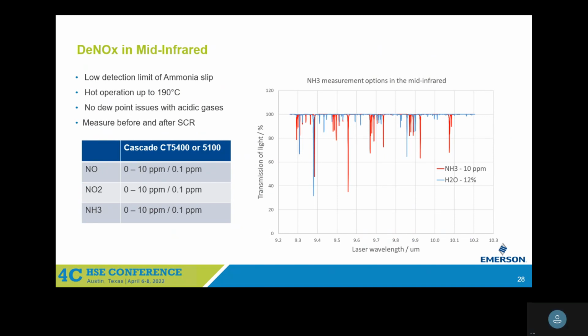A little bit about ammonia. Ammonia slip has traditionally been measured nowadays with tunable diode lasers cross stack. The reason is to avoid an extractive system with a molecule as sticky as ammonia. So they've solved that problem, but they've created another problem, and that is they're measuring in the near infrared. Near infrared has a lot of water interference where those ammonia peaks are. So we operate in the mid infrared. That's where the quantum cascade lasers reside. Mid infrared has very strong primary peaks. They're strong and they're narrow, so they give us very good resolution so that we can do direct absorption spectroscopy.